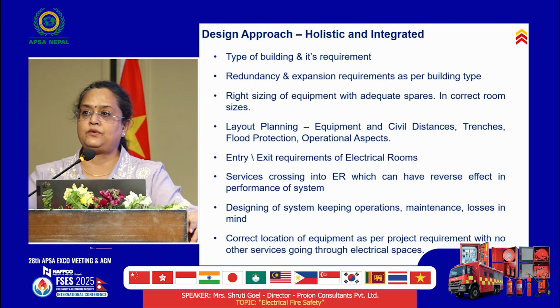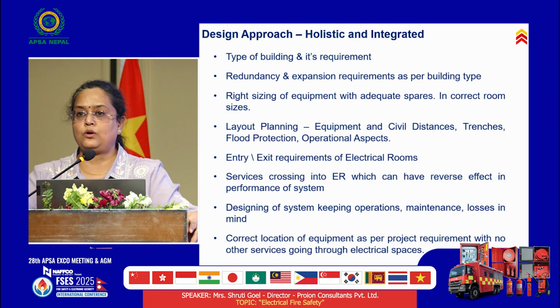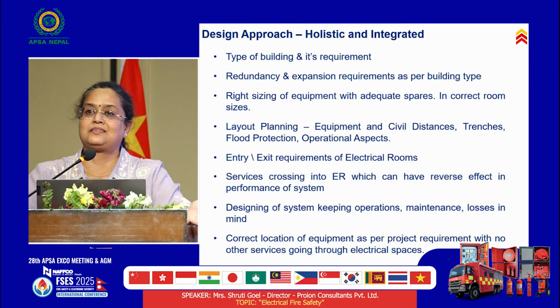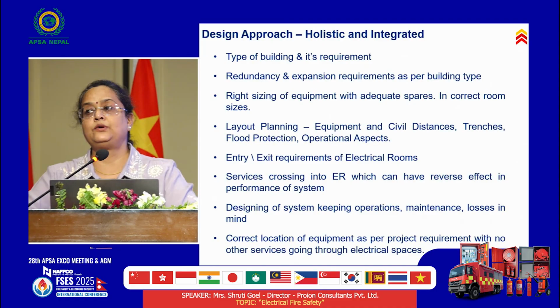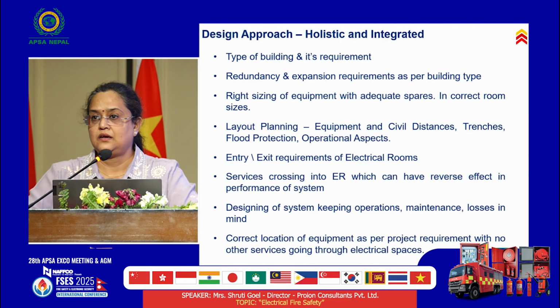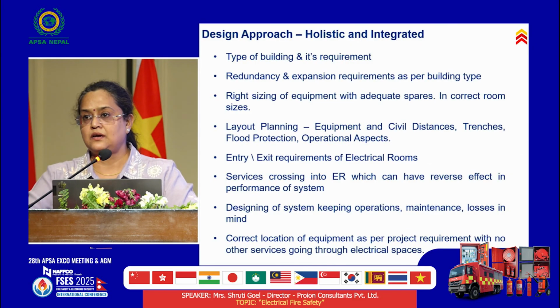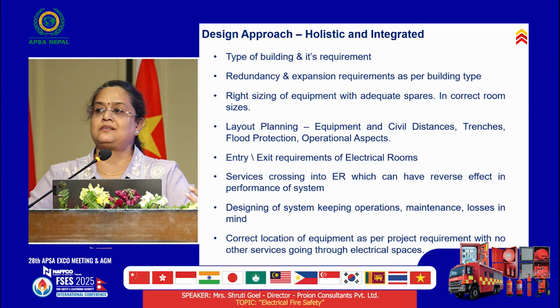Banquet hall and rooms will have minimal load, but the major bulk load should all be kept near the substation, so that you're reducing cable lengths and also reducing the fire risk. So whenever you're designing your systems, design should be optimized, and if it's optimized, the risk of fire will be less.